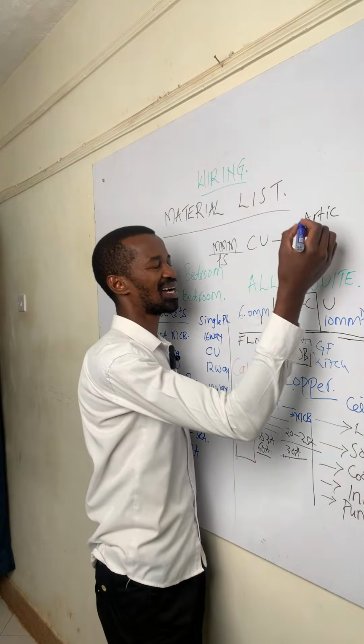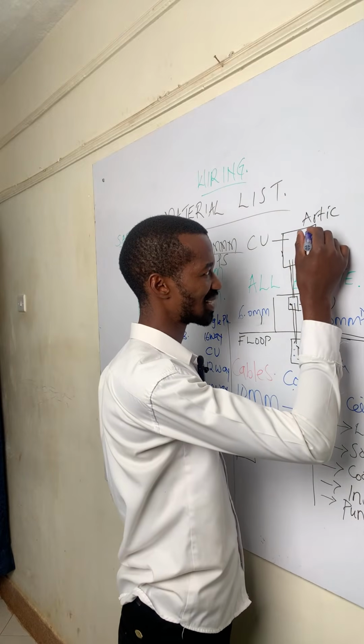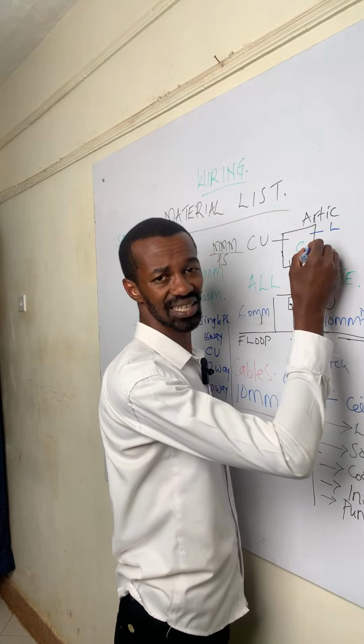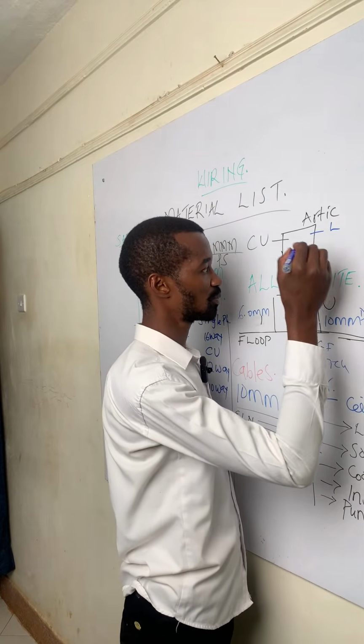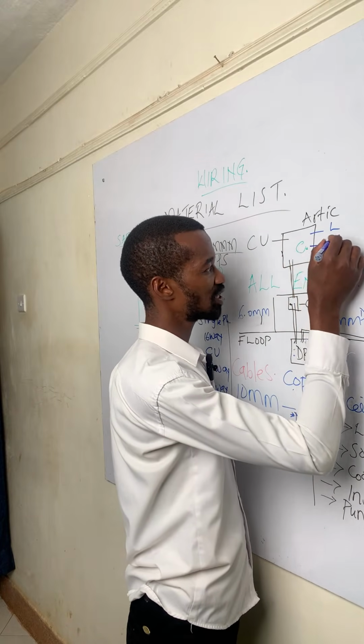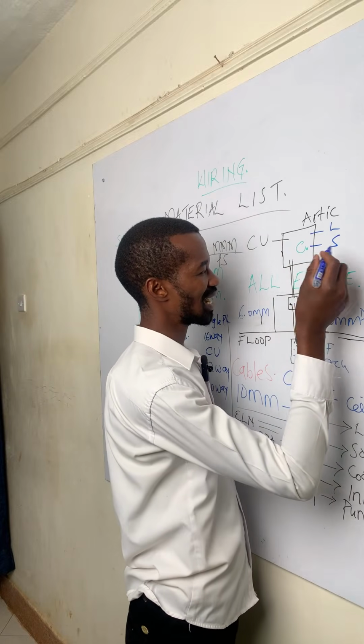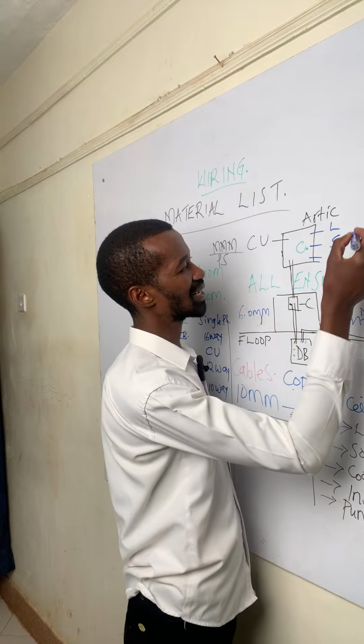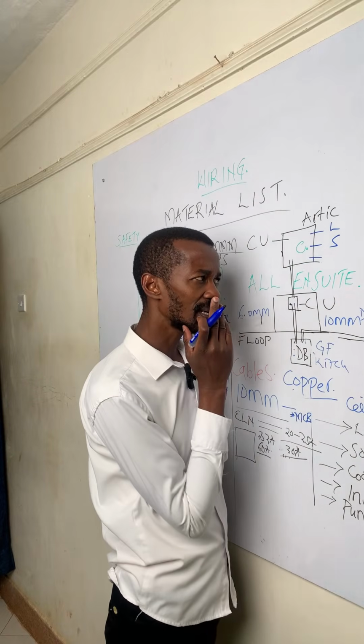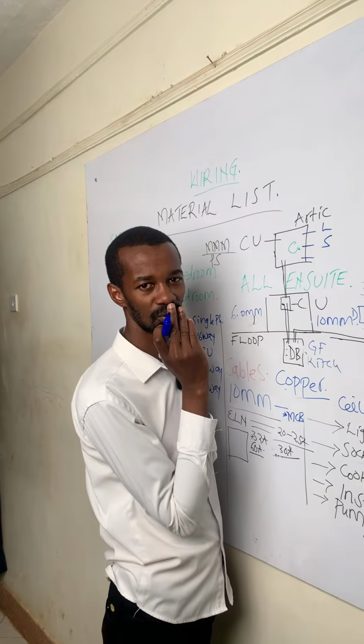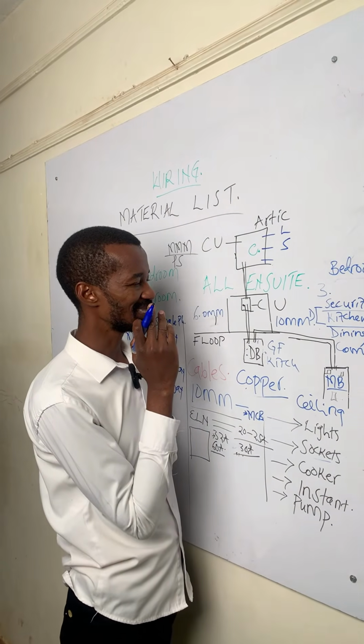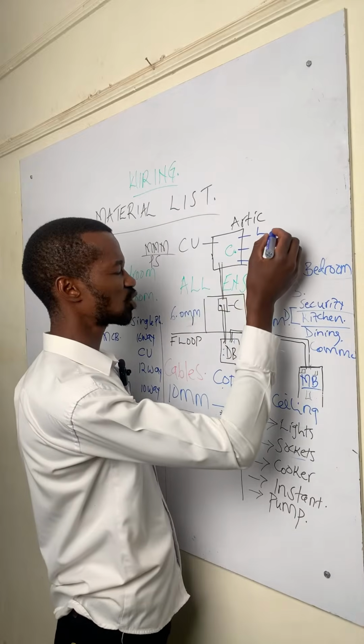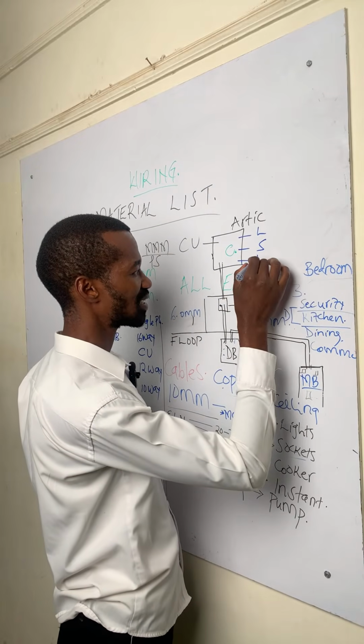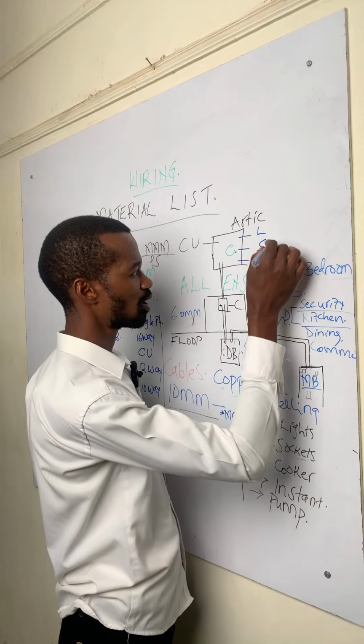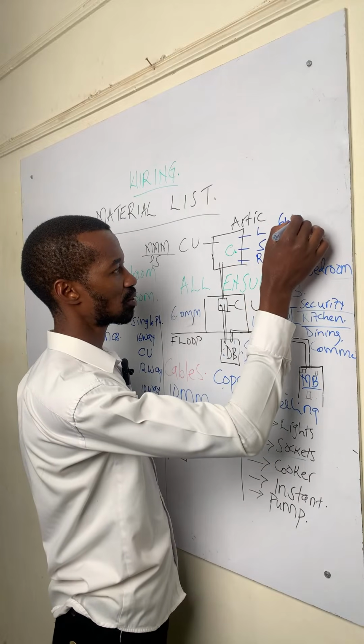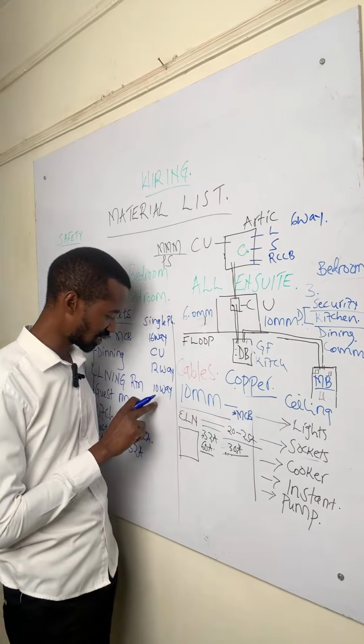You may ask, how many circuits do we have in the attic? We have lights - even if it's a single bulb, that is a circuit and has to be protected independently. For the sockets, remember in the attic you can have something else, even powering a pump in the ceiling. Can we have a pump in the ceiling really? I'm not so sure, maybe it makes a lot of noise, but I think you can have something else - an RCCB in there. So probably you require a 6-way consumer unit, not a 10-way like I've indicated here - that might be too much.